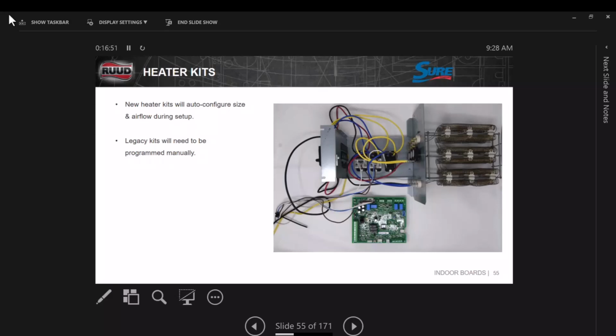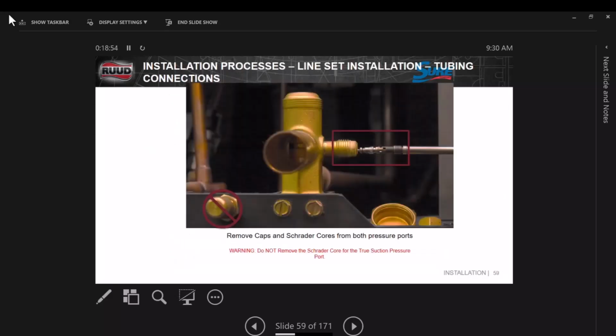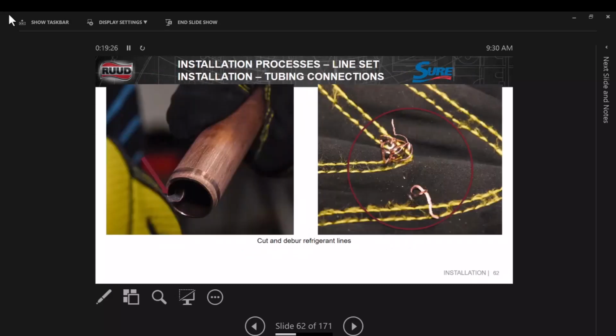Now, installation process. Let's start at this. Now, this is going to be elementary to some of you. You know, we start off by taking out all the Schrader valves, right? Because when we heat this thing up, it's going to do what? It's going to melt, right? We need to deburr these things, being careful not to get any of the shavings down inside. If you don't deburr it, you know, smaller tube copper, it could show some type of restriction there, especially when we're trying to flow a high velocity amount of refrigerant.